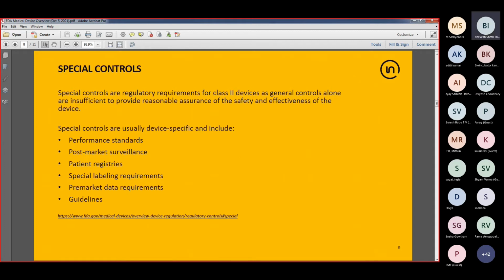Then we get into special controls. These are regulatory requirements that are mostly for class 2 devices because general controls alone are not sufficient to provide reasonable assurance of safety and effectiveness for class 2 device. So the special controls typically include performance standards, post-market surveillance activities, patient registries, special labeling requirements, pre-market data requirements, and lastly, the guidelines. FDA has published a number of device-specific guidance documents. If you go to the FDA website, you can find a guidance document on surgical masks, respirators, ventilators. You can find guidance documents on CT scanners, MRI machines. So although there isn't a guidance document available for every medical device type, there are many that are available, especially when you're dealing with special controls.